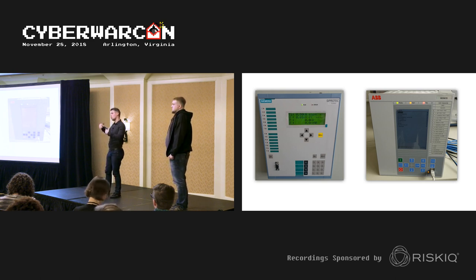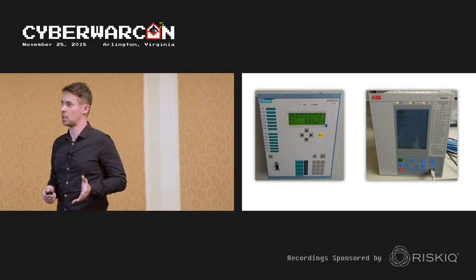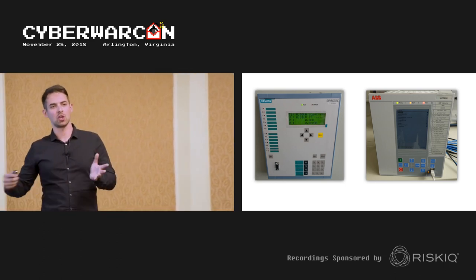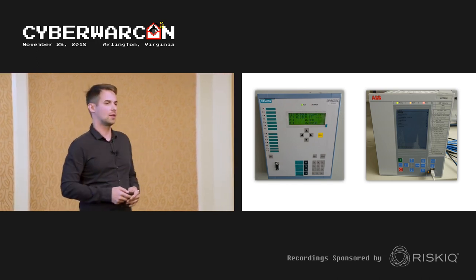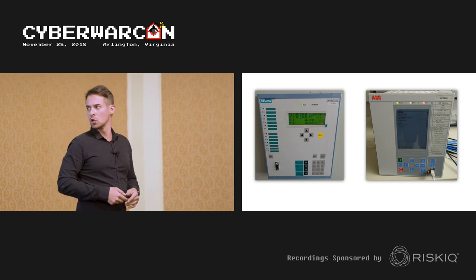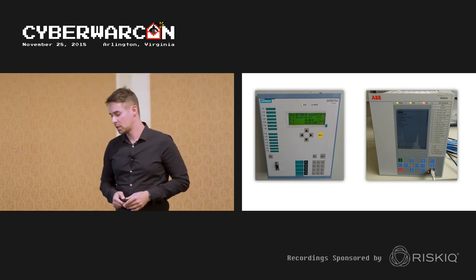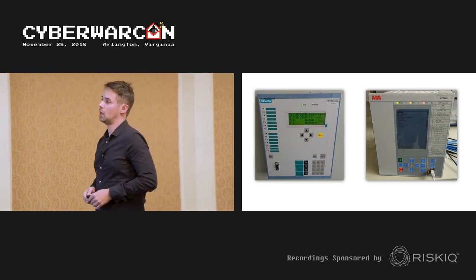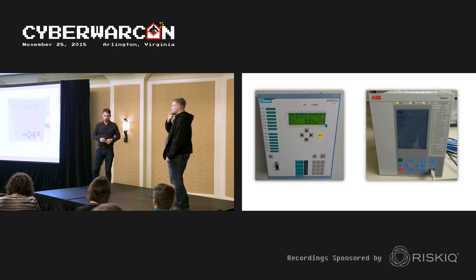It was sending commands to these devices to open circuit breakers in an endless loop. That was its primary functionality, which ultimately de-energized the substation. There was also denial-of-service functionality against Siemens exploiting a vulnerability, and wiping functionality to make recovery from the attack much harder.